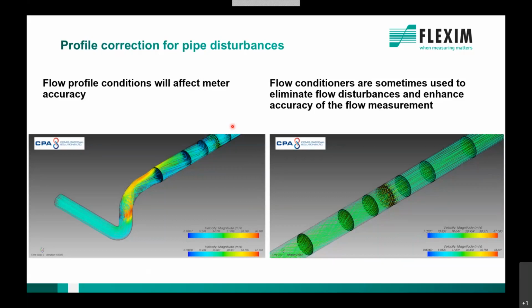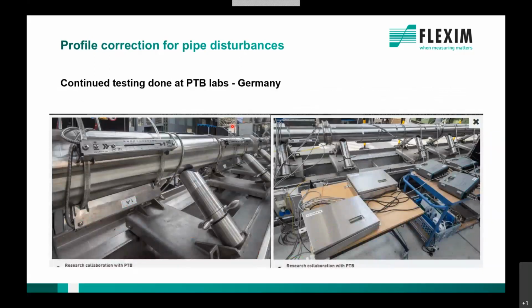That means we have to take the application as it is, and we normally install, in case of a retrofit, measurements where a flow meter was never considered to be installed on that pipe. That means in such a case, having an undisturbed flow profile is almost never the case, because they keep the distances short, and we have to install flow meters where we have maybe just enough room to make the installation itself, so that there are enough straight lengths. That's quite rare. That means most of our installations have to deal with a disturbed flow profile, and the question is, how accurate is my measurement when I have to install it like that? That's a question people are always faced with when installing flow meters. We give those people an answer now with our function.